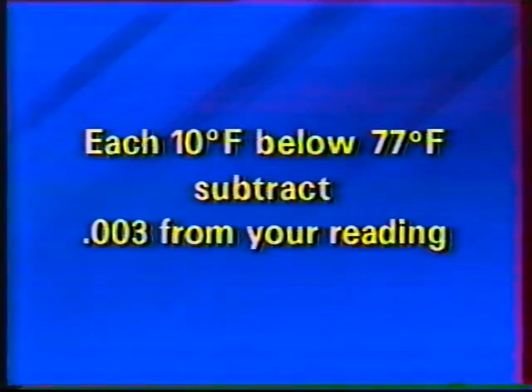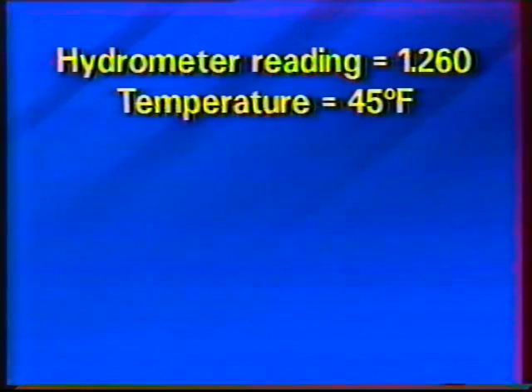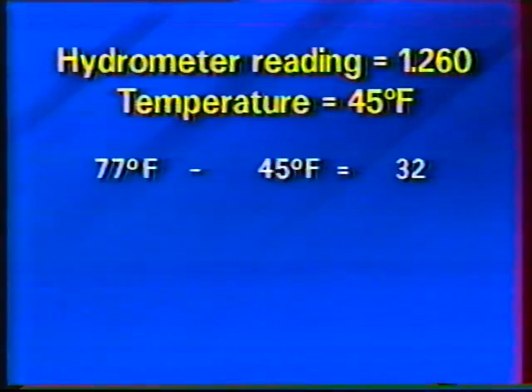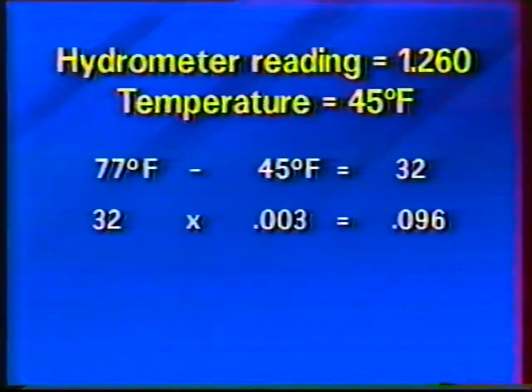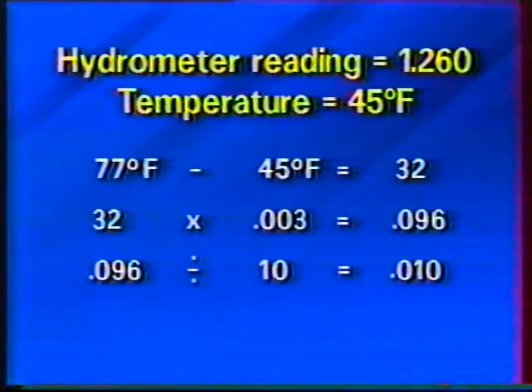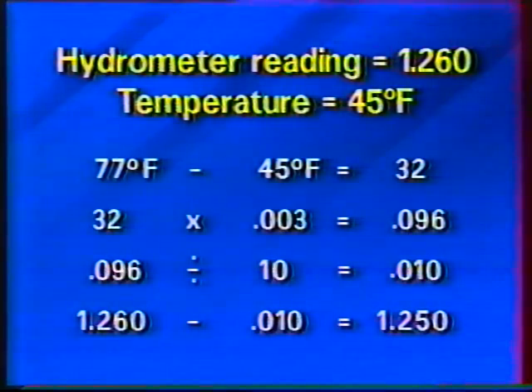For each 10 degrees below 77 degrees that the electrolyte reads, you subtract 0.003 from the hydrometer reading. For example, let's say our hydrometer reading is still 1.260, but our temperature is 45 degrees. We subtract the temperature, 45 degrees, from 77, multiply that by 0.003 and divide by 10. This gives us 0.010 rounded to the third decimal place, which we subtract from our original reading to get the true reading.